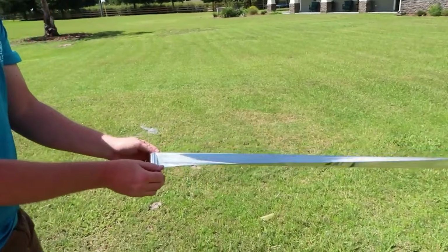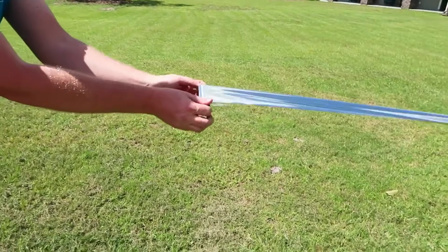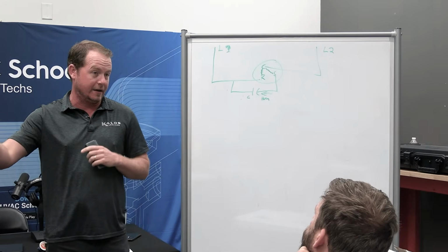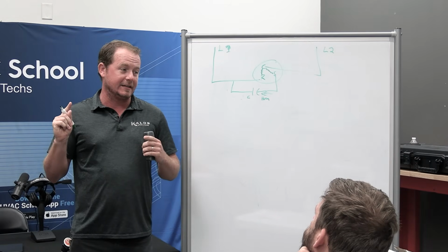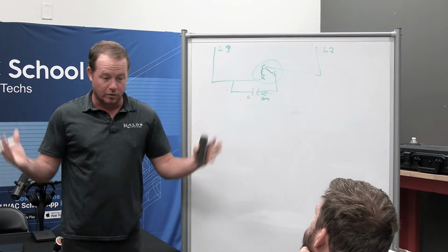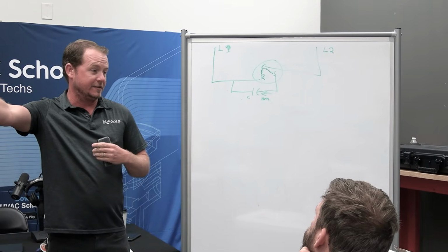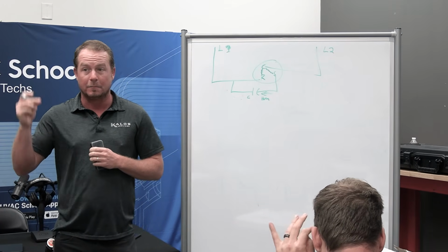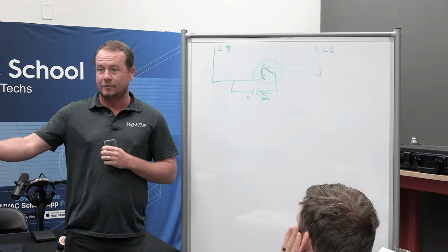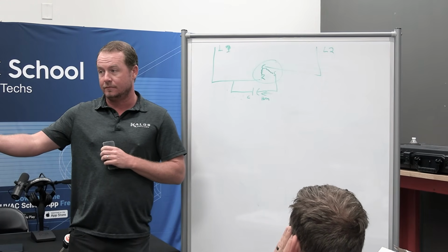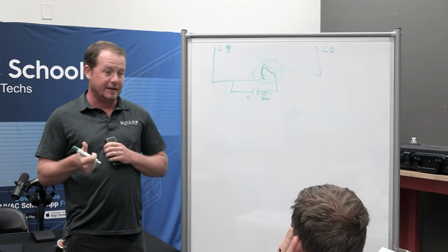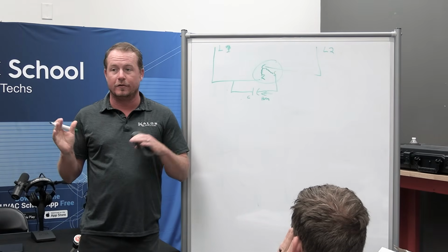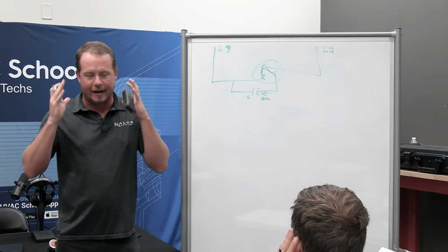The electrons store and discharge, store and discharge. So in that sense, it is like a battery, in the sense that it stores energy. But it's not like a battery in the sense that with a battery, we store energy and then we release it slowly over time. In a capacitor, we're storing it and releasing it 60 times per second, completely. Completely storing, completely releasing 60 times per second. We're doing that, yes, because it creates a phase shift, which helps create kind of that third hand to spin a motor. If you imagine, the best way I've always thought of it.